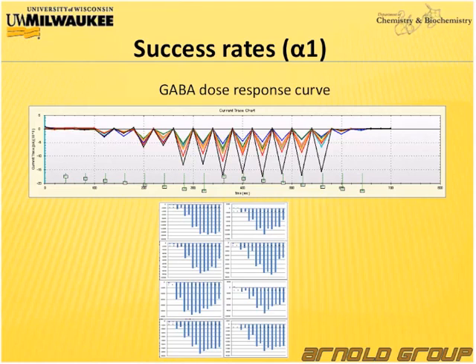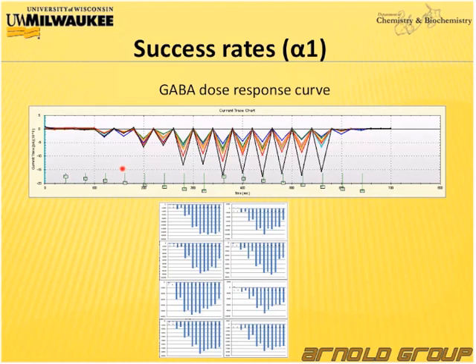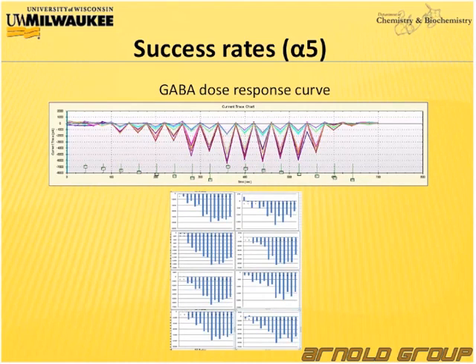In the second part of my talk I want to address some technical aspects, starting with success rates. Shown here is a screenshot from the IonFlux software, where the different colors represent different ensembles. The absolute value of the induced negative current for each ensemble is different, but the relative relationship — meaning the calculated EC50 value — is the same. As shown in the Excel plot, the dose response of each ensemble is the same even if the absolute response differs. Another example makes this clearer: some ensembles show high response, others significantly smaller, but all show a very nice dose-response relationship.